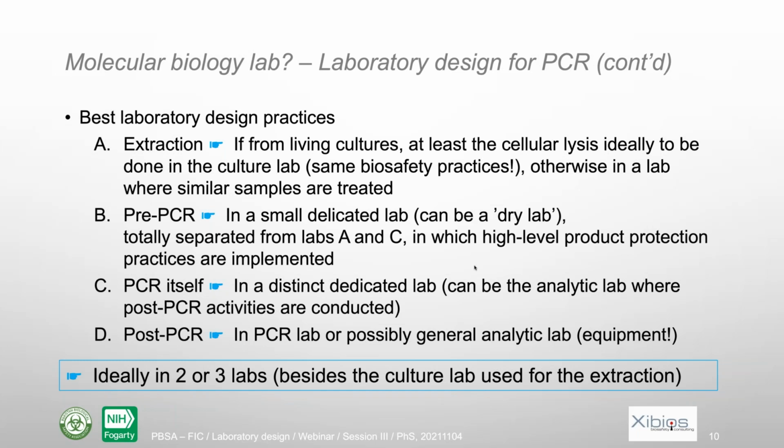Okay? Then the pre-PCR, that's the crucial activity where you cannot have any contamination. It should be in a small, dedicated lab. That lab should be totally separate from the extraction, if possible, but mostly from the PCR itself. And in that lab, you should have really high-level product protection practices in place.